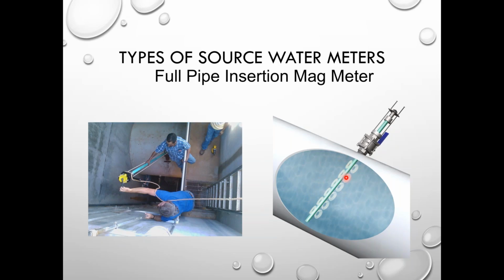And we're just essentially measuring it with an electromagnetic velocity sensor with coils that are spaced out evenly along the flow pattern here. You can see these are made very, very large in size. And the good part is that they're very, very light. They're easy to install. And they also have a very good turn down ratio. It's a 40-to-1. So the range of this flow meter is 4 times the range of a typical prop meter.